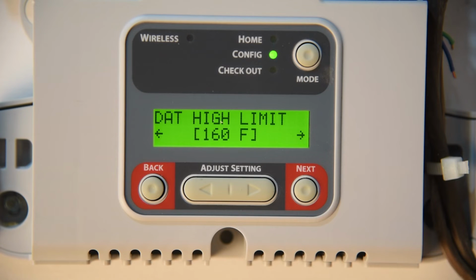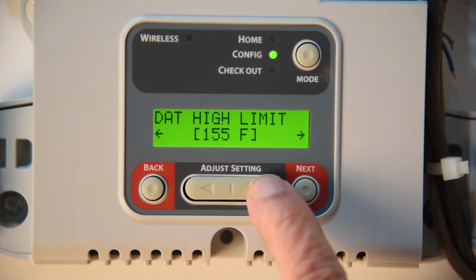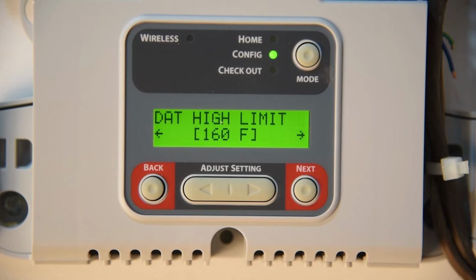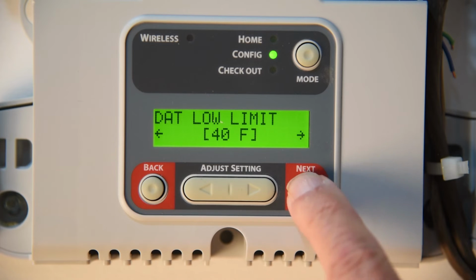Let's hit next. You have a high limit of 160. The manual says anywhere from 110 to 180. If I go like this, you see it goes in 5-degree increments. 160 is the recommended. That's what I'm going to leave it at. Next is the low limit. Low limit is 30 to 60. Well, my air conditioning normally operates in a range of 55 down to about 50 degrees. So I'm going to leave it at the recommended 40. Hit next.